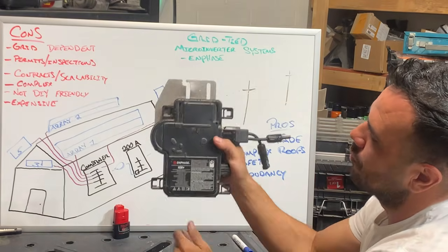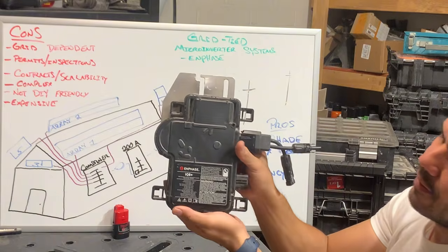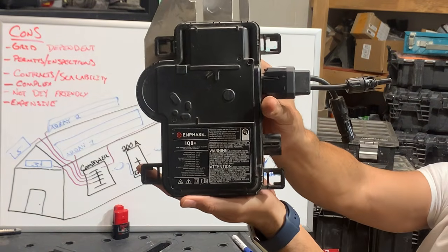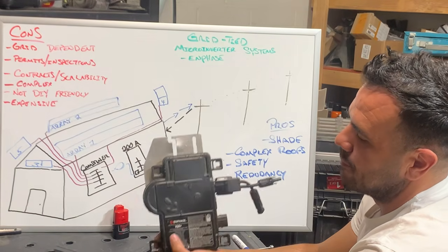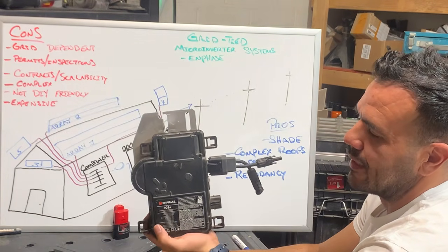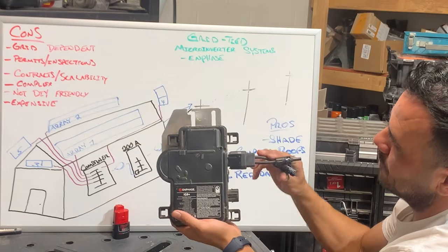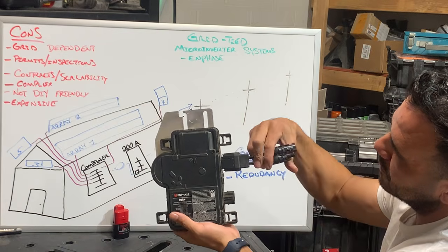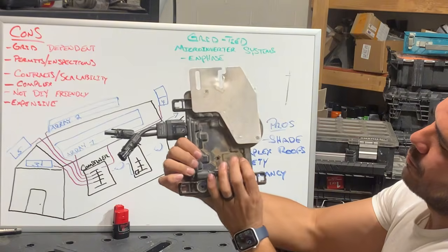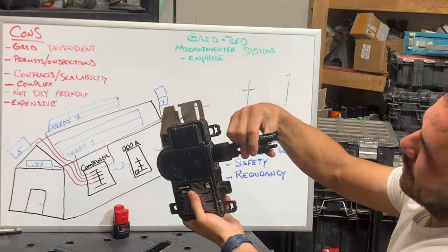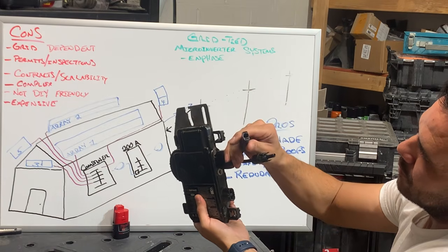Each one of our 15 solar panels is going to have a microinverter just like this one right here. This is an Enphase IQ8 Plus. Because we're sticking with the Enphase, we're just going to use this as an example, but you'll see a bunch of different brands, and they'll look somewhat similar like this. You'll have your inputs for your DC. This is where our solar panel is going to hook up. Each one of these will be mounted somewhere on the back of a solar panel. And our solar panels' MC4 connectors will connect right onto this plug here, where we would connect our DC inputs.